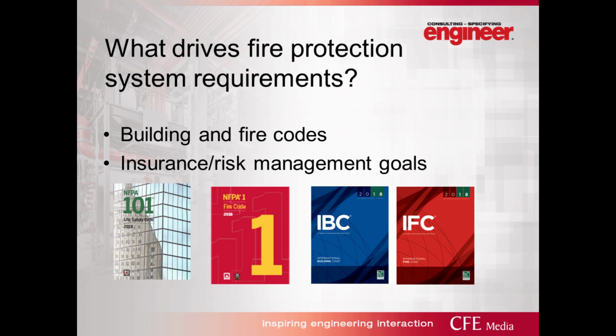So without further ado, let's talk about what drives fire protection system requirements. When we talk about when a system is required, whether it's fire alarm or suppression, or what type of devices are required in a building, those requirements come from building and fire codes. So if you're dealing with the International Building Code or International Fire Code, those documents have requirements for fire suppression and fire alarm, as well as NFPA 101 and NFPA 1. There may be other occupancy-specific standards that could drive a requirement for a specific type of fire protection system. There also may be insurance or risk management goals that may drive requirements for fire protection systems.